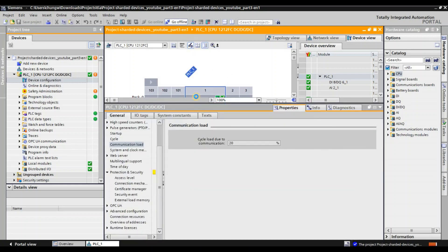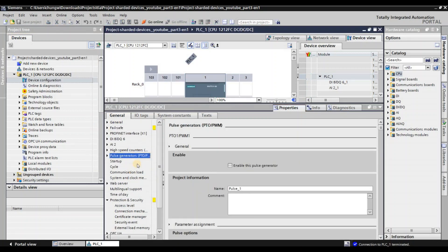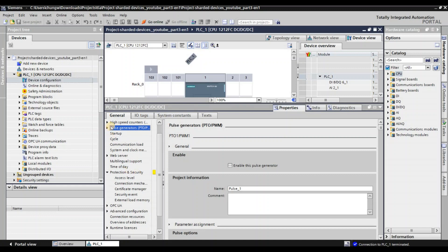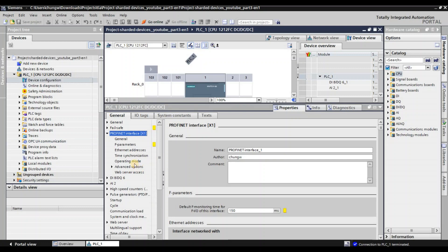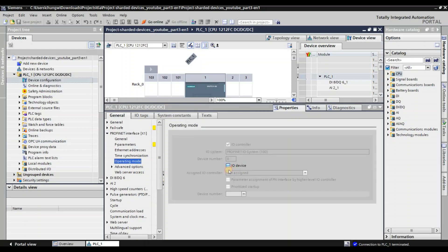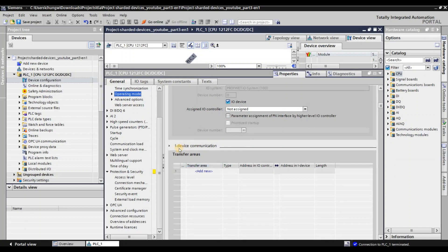We need to go offline first. The first thing we need to do is enable the IO device function. To do it, go to the Profinet interface X1, browse to the operating mode, and check the IO device checkbox. Now you can see below there are iDevice communication fields.